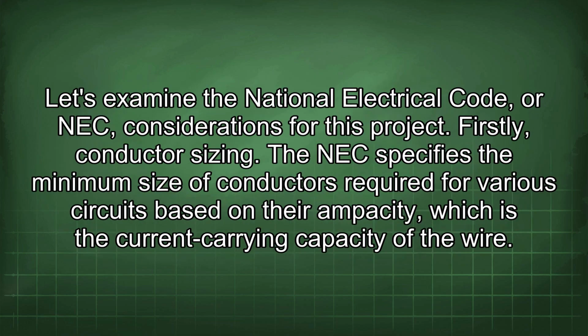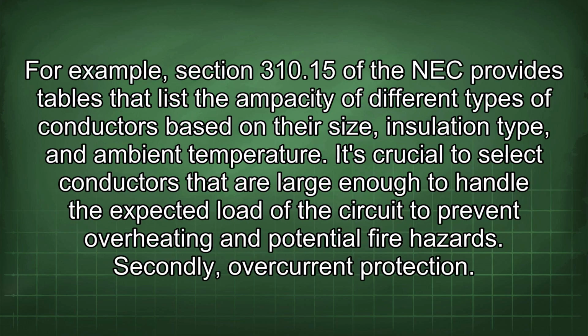Let's examine the National Electrical Code, or NEC, considerations for this project. Firstly, conductor sizing. The NEC specifies the minimum size of conductors required for various circuits based on their ampacity, which is the current carrying capacity of the wire. For example, Section 310.15 of the NEC provides tables that list the ampacity of different types of conductors based on their size, insulation type, and ambient temperature. It's crucial to select conductors that are large enough to handle the expected load of the circuit to prevent overheating and potential fire hazards. Secondly, overcurrent protection.